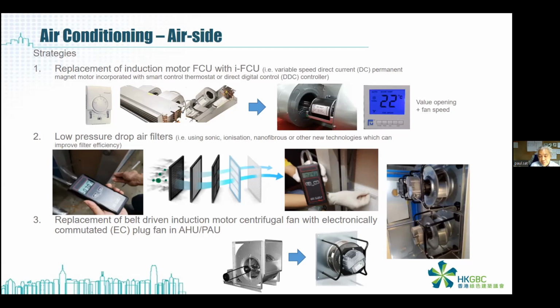The second point is that they use direct current, so when you want to change the speed of the fan, you do not need to install a frequency inverter. You can directly change the current and voltage of the power. The third point is that this kind of fan has better fan motor efficiency and power performance. They can reduce the speed much lower than belt drive centrifugal fans. So this is also very common.